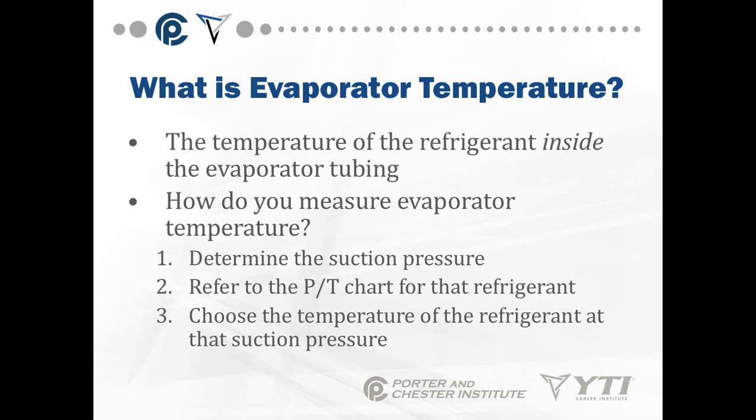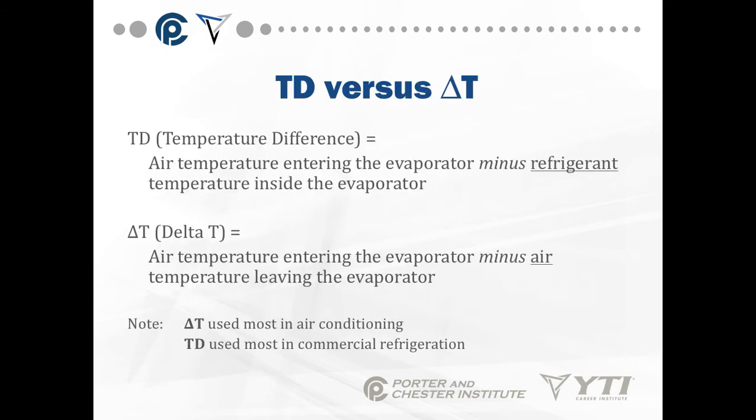The evaporator temperature is the temperature of the refrigerant inside the tubing. To measure evaporator temperature, determine the suction pressure and refer to your pressure-temperature chart for that refrigerant. Choose the temperature of the refrigerant at that suction pressure — it's basically a conversion, changing your suction pressure (your low-side pressure) to temperature using the appropriate chart.